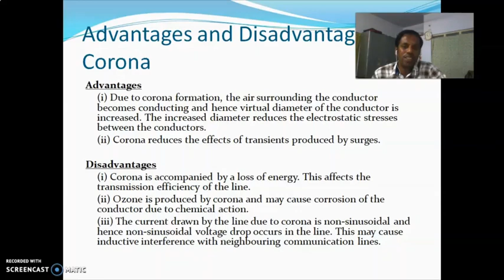The second one, ozone is produced by corona and may cause corrosion of the conductor due to chemical action. The third one, the current drawn by the line due to corona is non-sinusoidal and hence non-sinusoidal voltage drop occurs in the line. This may cause inductive interference with the neighboring communication lines. So harmonics will be created. It will cause electromagnetic interference, EMI, with the neighboring communication lines. So even though corona has advantages, we have to reduce the corona because corona has more disadvantages. The loss of energy is very, very important.